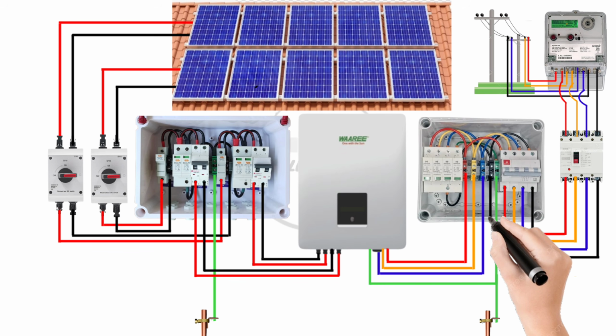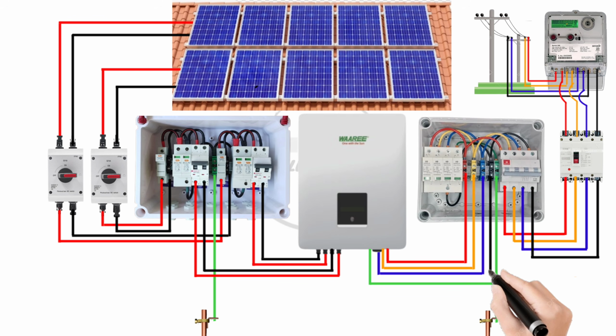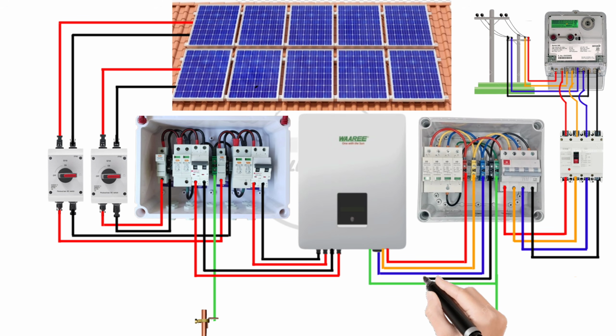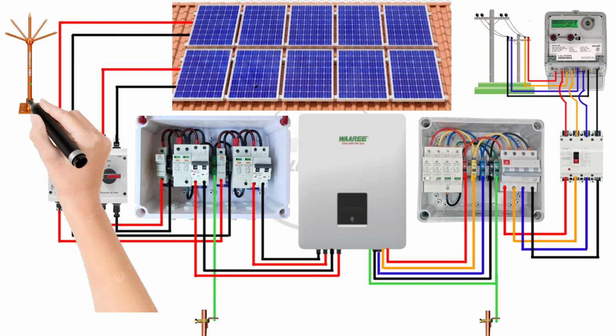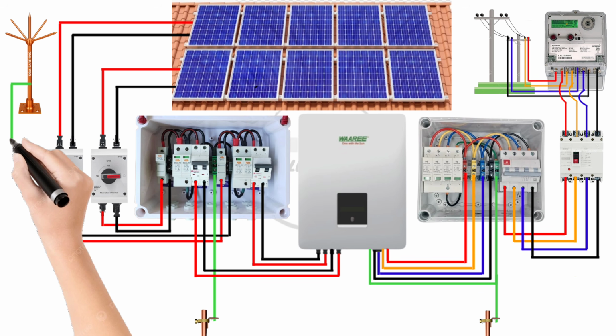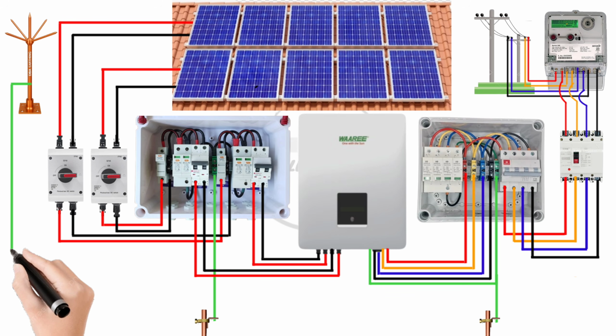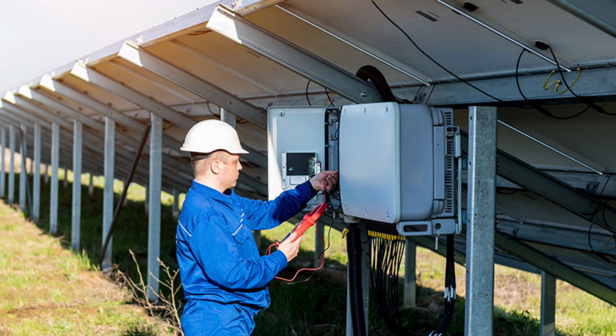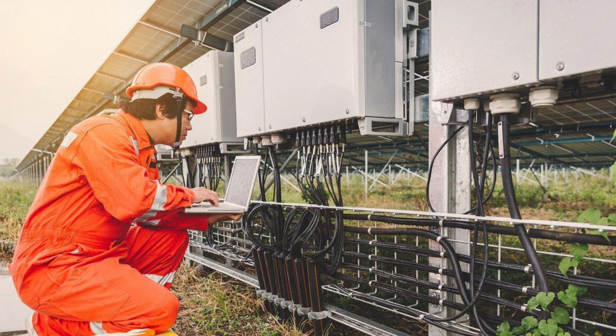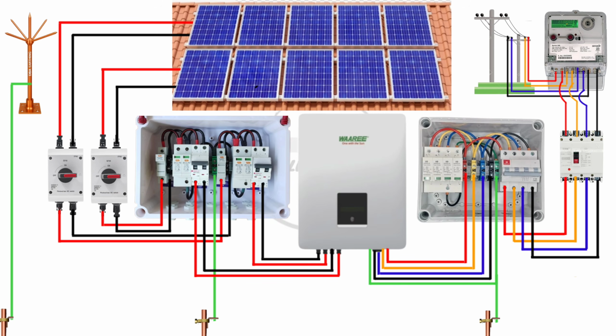Finally, the output of the MCB is connected to the AC input terminal of our 5 kW inverter. The inverter converts DC electricity generated by the solar panels into AC electricity that can be used by your home or fed back into the grid. Now connect the terminal from the lightning arrestor to ground for safety of the solar PV system from lightning strikes. Remember, each of these connections must be made securely and according to all local electrical codes. Use appropriate size cables and ensure all connections are tight and correct. After the connections are made, test the system, verify the voltage at various points, check the operation and ensure the inverter is functioning correctly. And that's it. You have now successfully connected your 5 kW AC side grid tie solar system.